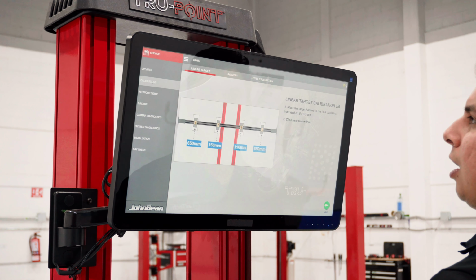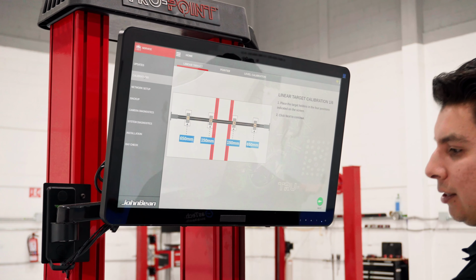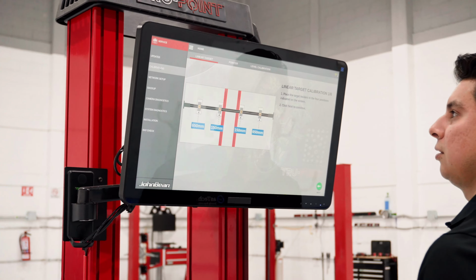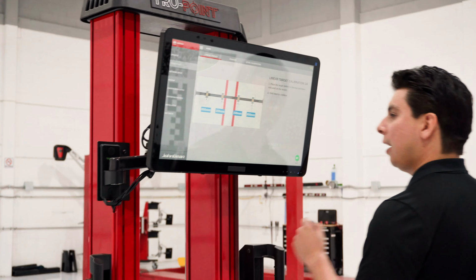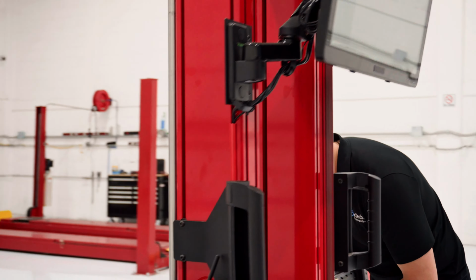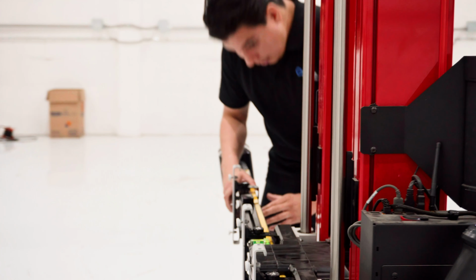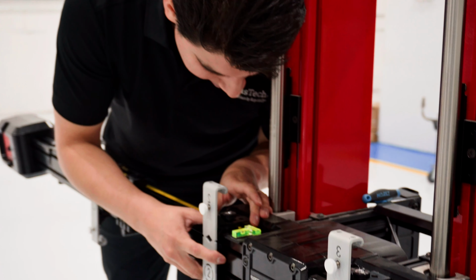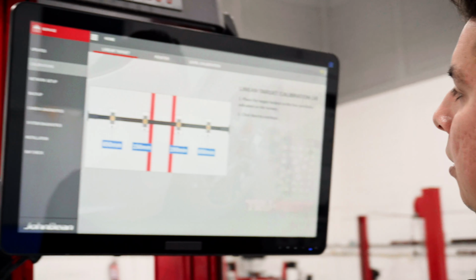Then open Calibrations and select Linear Target. Tru-Point will guide you through the process by asking you to position the sensors to specific measurements along the bar. Move each sensor to the exact value shown on screen. Once it's set correctly, tap Next to continue.